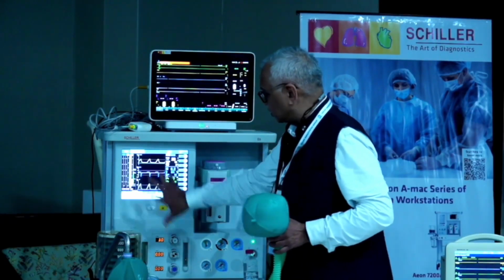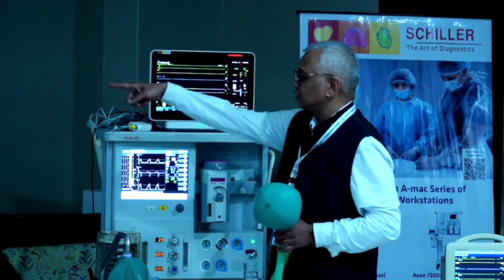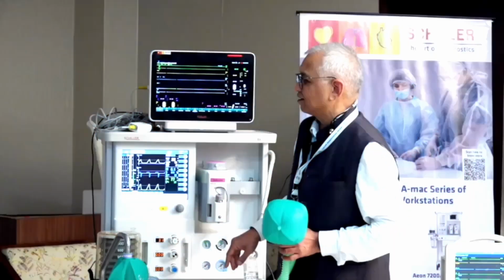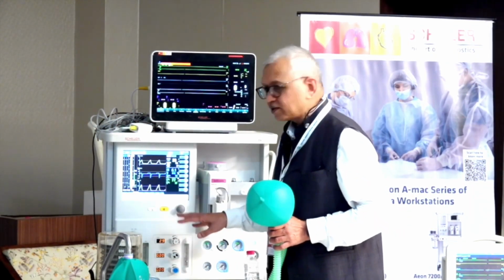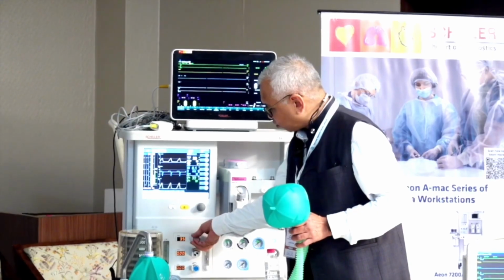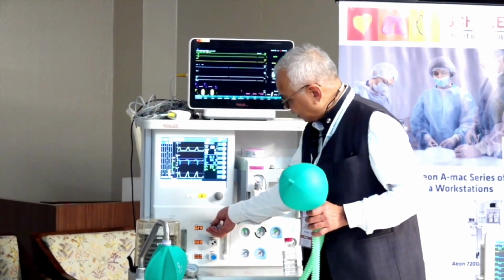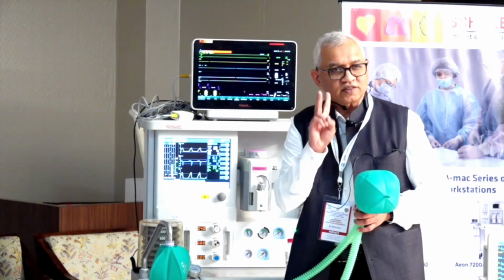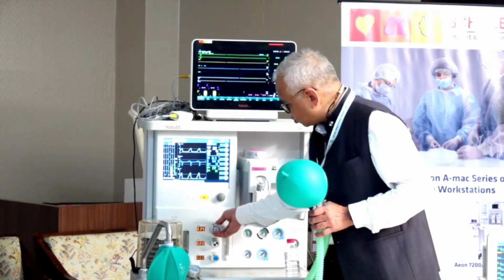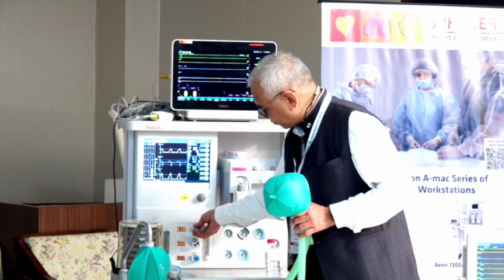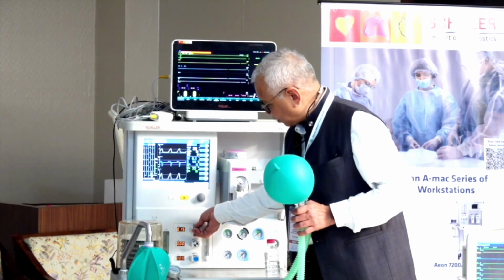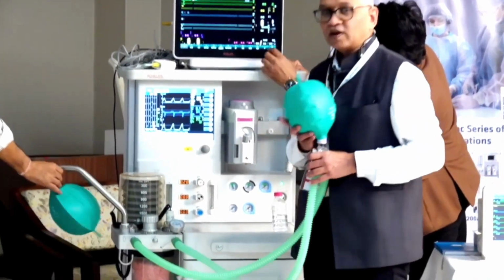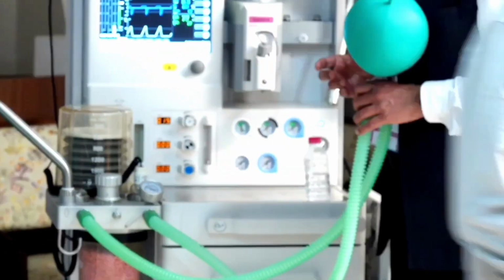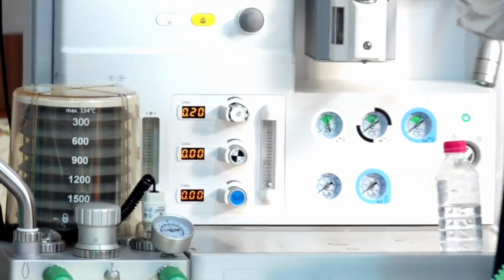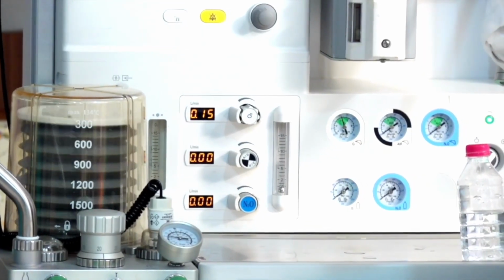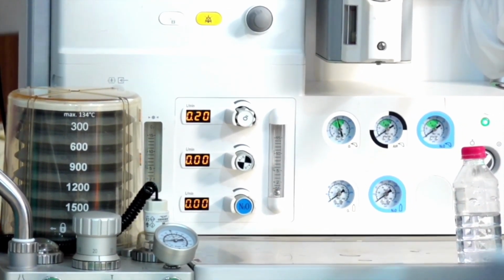If you can zoom in here on this part, you don't need to show me. Show this part. So I'm keeping it at 3. Gradually you go down on the flow. Okay. And our target for low flow anesthesia is 200 ml. So we should take it down to 200 ml and check whether it is working or not. Okay. So it is working well. Right. So the leak is less than 200 ml.